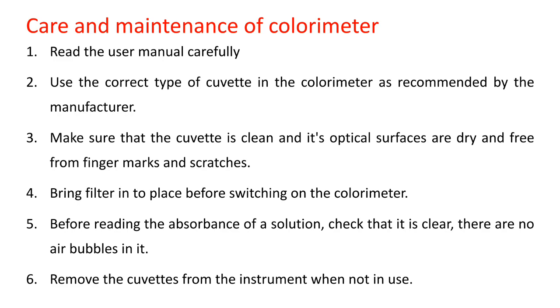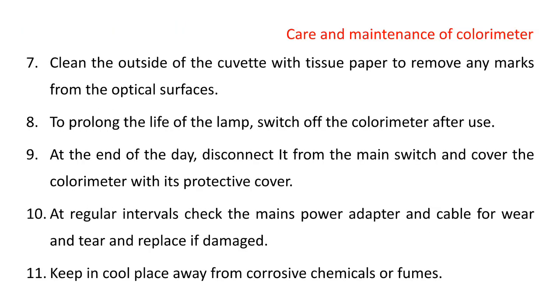Before reading the absorbance, check that the solution is clear with no air bubbles in it, and remove the cuvettes from the instrument when not in use. Clean the outside of the cuvette with tissue paper to remove any marks from the optical surface.